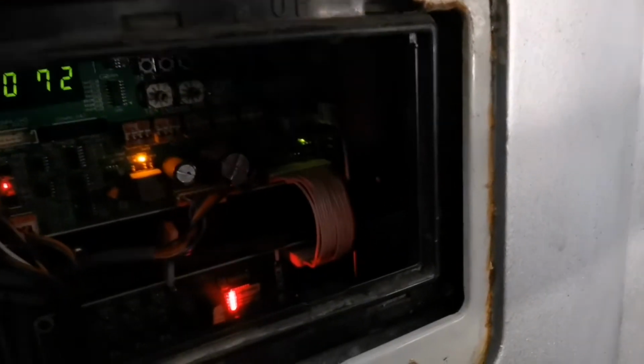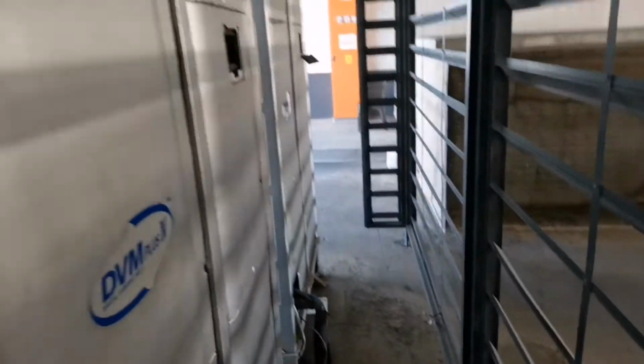This is a 20 horsepower condenser. This is a 16 horsepower condenser, so in total you've got 36 horsepower. Put that into kilowatts, you've got 40, let's say 45, and so you've got about 90, you've got 100 kilowatts of cooling capacity here. That's a lot.